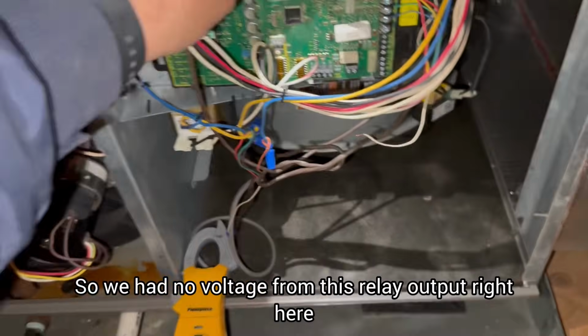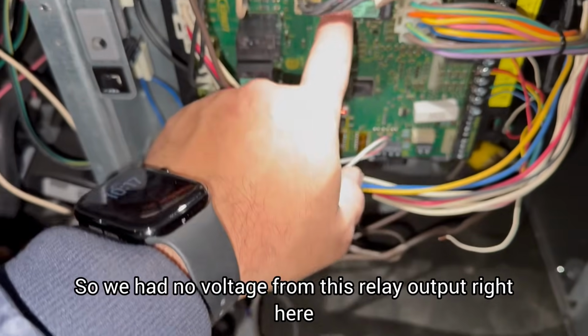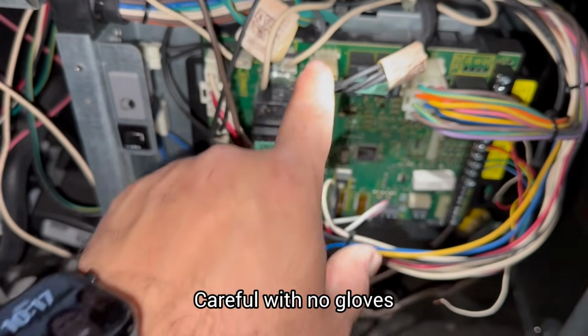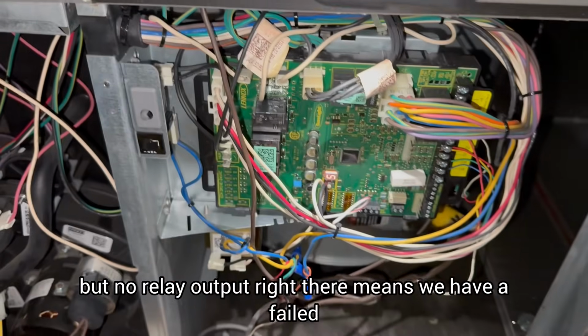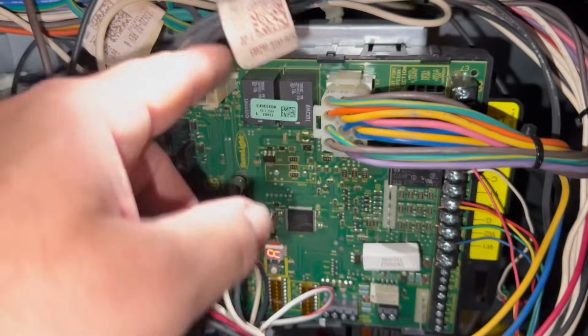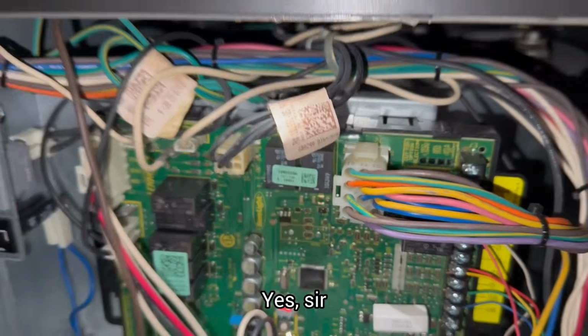So we had no voltage from this relay output right here. Careful, no gloves, but no relay output right there. It means we have a failed heating relay.